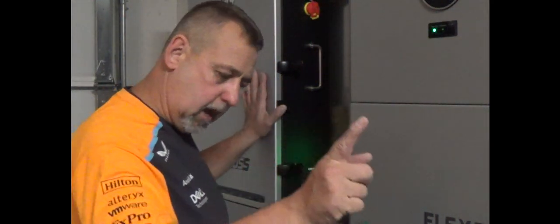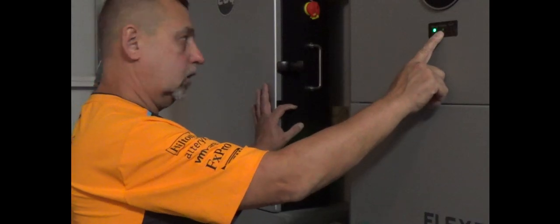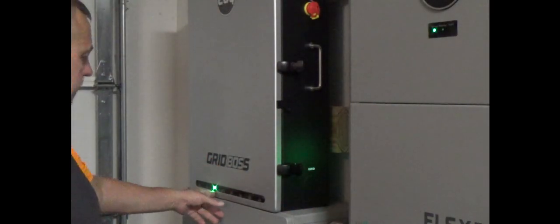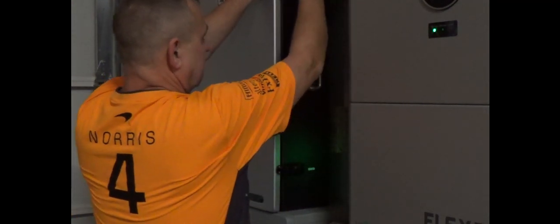Alright. Okay. Let's try this one more time. So, I enabled the Gridboss on the app on my laptop. When I did, I lost the warning here. I got the hybrid light here, and I also got my dongle blinking here for the Wi-Fi. I checked the voltage here. I have 240 volts, 120 on each leg. I also see I have some blue communication lights up here.